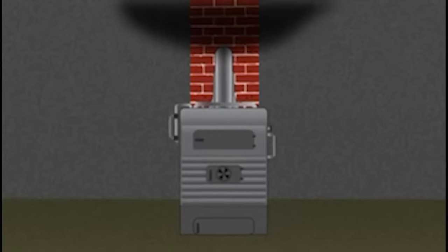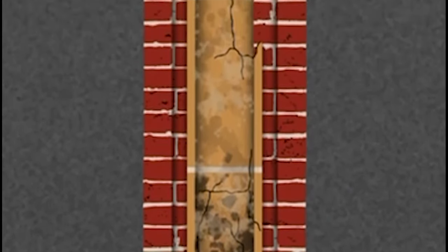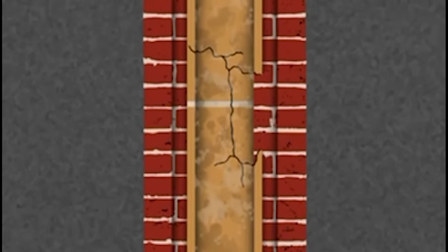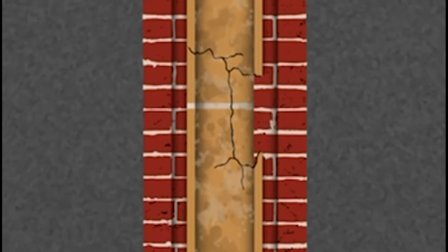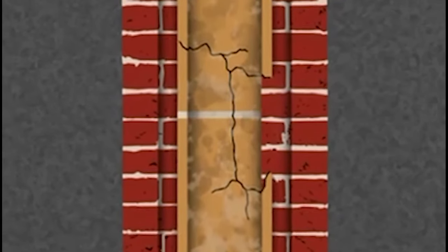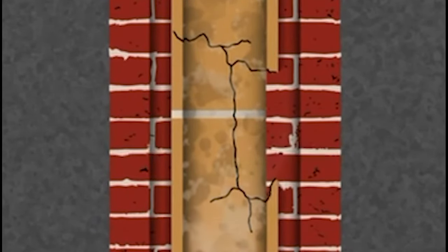When the terracotta rots and falls to the base, it creates blockage that causes a puffback of soot or carbon monoxide coming back into the home. Where each terracotta clay pipe once was is also a problem, because now there is a hole inside the chimney. Instead of it being airtight and venting correctly, it's now like a straw with a hole in the side.